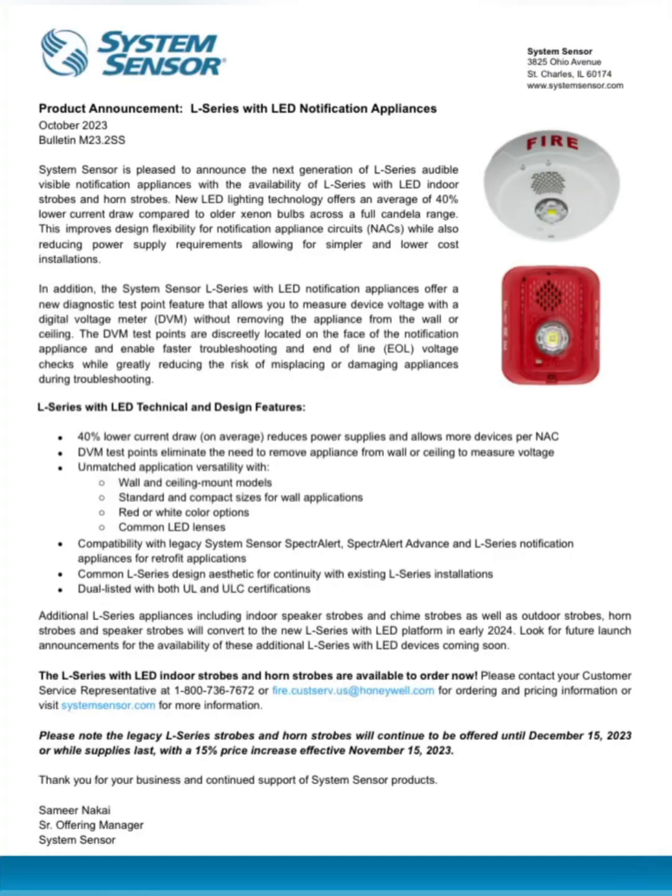I will mention a couple things. I'm not going to read the full documentation sheet, but here are the L Series LED technical and design features: 40% lower current draw on average, which reduces power supplies and allows more devices per NAC. DVM test points eliminate the need to remove the appliance from the wall or ceiling to measure voltage. Unmatched application versatility with wall and ceiling mount models, standard and compact sizes for wall applications, red or white color options, and common LED lenses. Compatibility with legacy System Sensor, SpectrAlert, SpectrAlert Advance, and L Series notification appliances for retrofit applications. Common L Series design aesthetic for continuity with existing L Series installations. And finally, dual listed with both UL and ULC certifications.